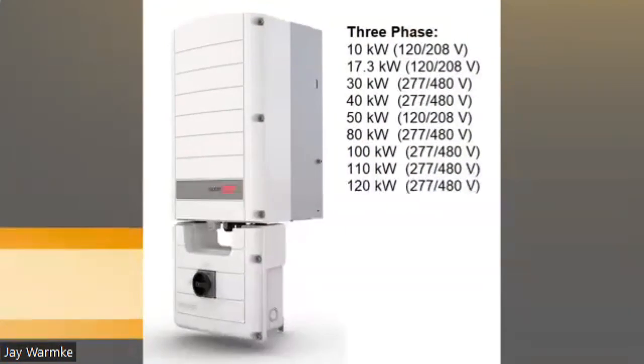And then the inverters, of course, when you get into a commercial system, are going to be 3-phase. And here in the US, there are the smaller ones, the 10 kW, the 17.3 kW systems, and then they even also have a 50 kW system that's 120/208 3-phase. But then you get into the bigger ones, 30, 40, 80, 100, 110, 120. Those are 277/480. So when you start getting into that, you're probably going to be having transformers on the site to step down the voltage, perhaps to a 208 3-phase, and then of course you'd be feeding those into three-phase panels.